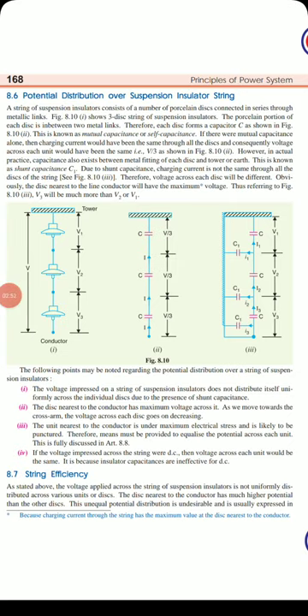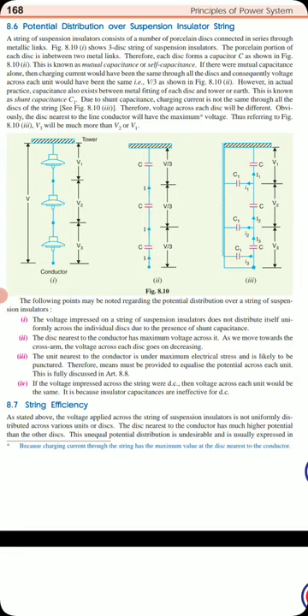Regarding potential distribution over a string of suspension insulators: the voltage impressed on the string does not distribute uniformly across individual disks due to the shunt capacitance C1. The disk nearest to the conductor has maximum voltage across it. As we move towards the cross arm, the voltage across each disk goes on decreasing. The unit nearest to the conductor is under maximum electrical stress.